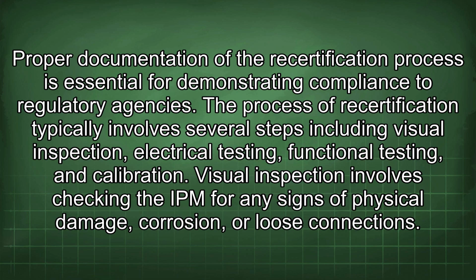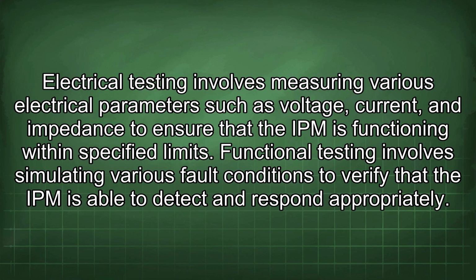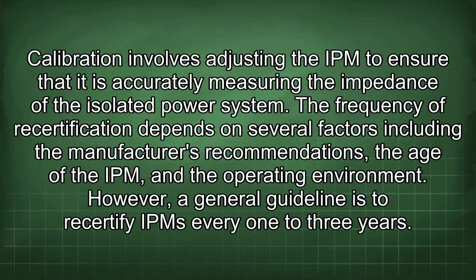The process of recertification typically involves several steps, including visual inspection, electrical testing, functional testing, and calibration. Visual inspection involves checking the IPM for any signs of physical damage, corrosion, or loose connections. Electrical testing involves measuring various electrical parameters such as voltage, current, and impedance to ensure that the IPM is functioning within specified limits. Functional testing involves simulating various fault conditions to verify that the IPM is able to detect and respond appropriately.